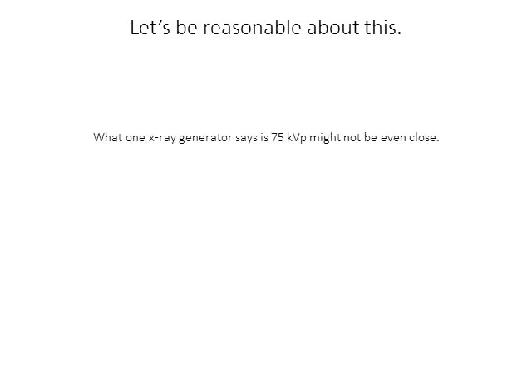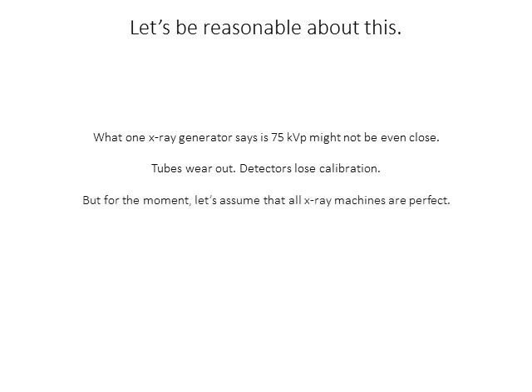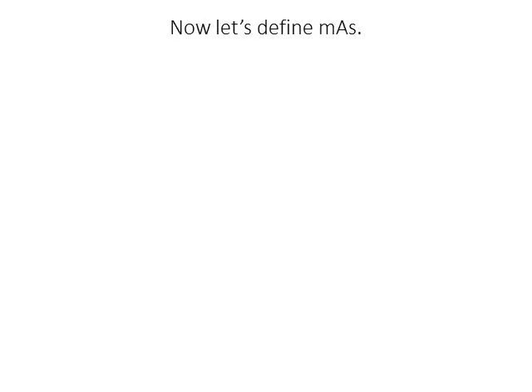What one generator says is 75 KVP might not be close in practice. Machines fall out of calibration, so these values are discussed conceptually. You might use 75 KVP in one center, go to the next center with the same exposure setting, and the KVP won't even be close. For the sake of this argument, we'll assume all x-ray machines are perfect.